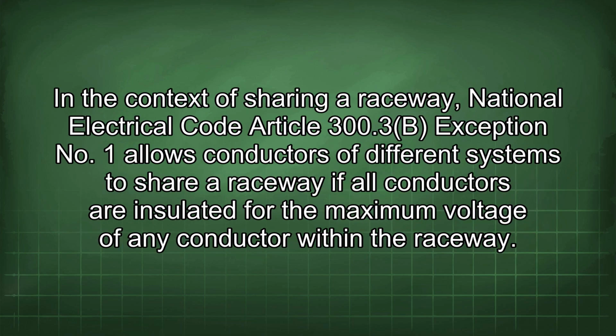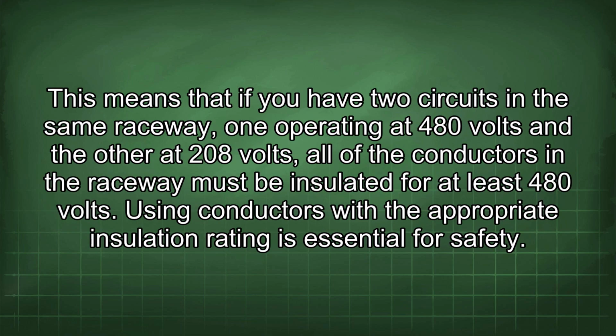In the context of sharing a raceway, National Electrical Code Article 300.3(B), Exception No. 1 allows conductors of different systems to share a raceway if all conductors are insulated for the maximum voltage of any conductor within the raceway. This means that if you have two circuits in the same raceway, one operating at 480 volts and the other at 208 volts, all of the conductors in the raceway must be insulated for at least 480 volts.